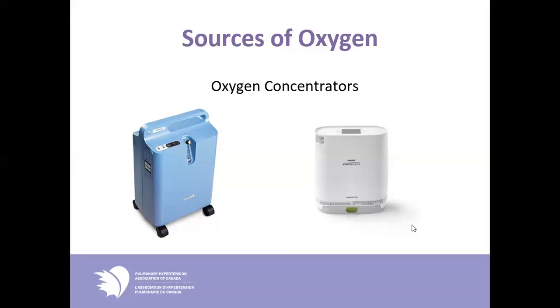On the right is a portable oxygen concentrator. The stationary blue one weighs about 30 pounds; the portable one weighs about six pounds with an extended-life battery. Same idea — it produces oxygen by drawing it in and separating it — but it's portable. You can get a backpack or shoulder strap and off you go. It's kind of the latest and greatest as far as technology is concerned. The downsides are they make the same sort of noise, which some people get self-conscious about, and they work on lithium-ion batteries that slowly dissipate and don't hold their charge as well over time, but they really are a very useful tool.